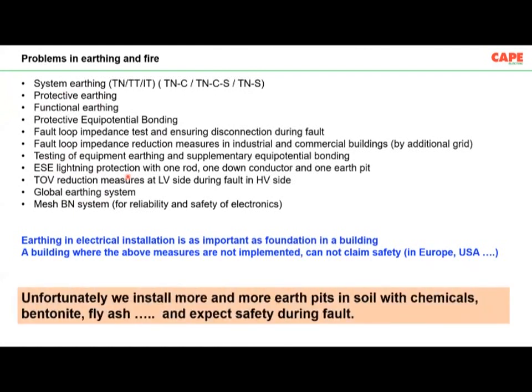And unfortunately, what do we do with respect to earthing? We install more and more earth pits in soil with chemicals, bentonite, fly ash, and expect safety during a fault. So actually, the subject of earthing has nothing to do with earth pits in soil. Earthing is a subject which is ensuring all these bullet points which I have put here: system earthing, protective earthing, functional earthing, and finally mesh BN. So this is how earthing must be carried out.